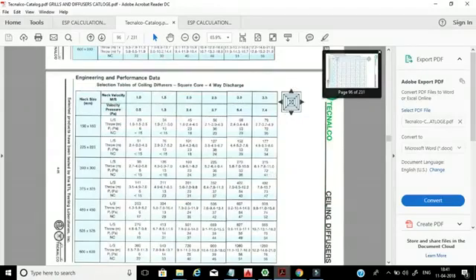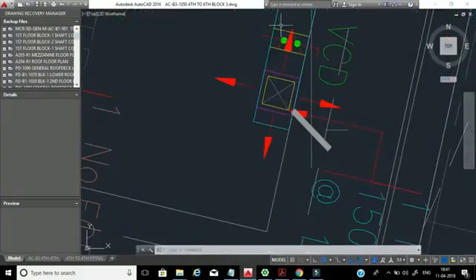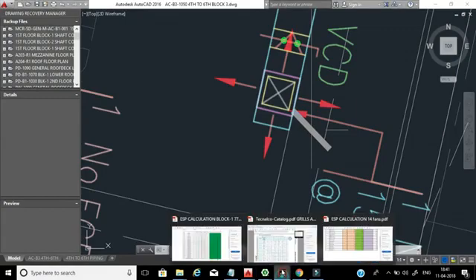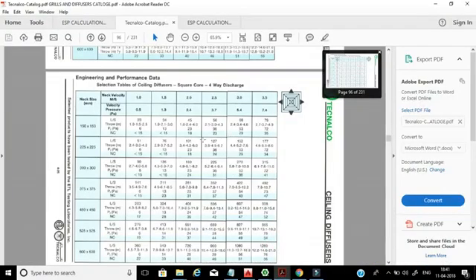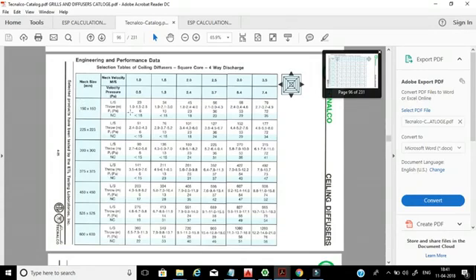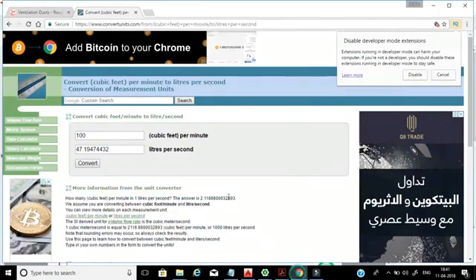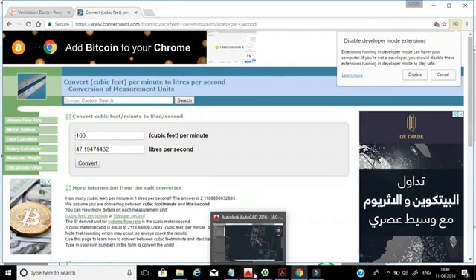We will go for four-way because in the drawing it is clearly mentioned as four-way — you can see four arrows. The neck size is 150 by 150 and our flow rate is 100 CFM, which equals 47 liters per second. Looking in the catalog at 150 by 150 neck size, the nearest values are 45 and 56 liters per second. We can go for 45 — there is no problem. But a very important thing is the noise criteria. For villas and bedrooms, the noise criteria should be less than 15; at maximum, in the worst case, less than 20.